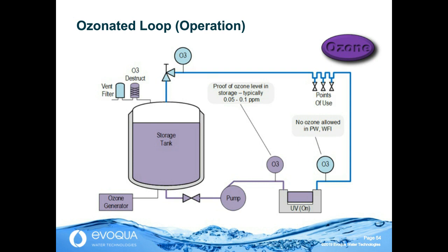Ozone is growing in pharma water at a very rapid rate. And here, this is a very simplified drawing, so it is not reflecting details of how the ozone is introduced into the tank, but in principle, the tank is always under protection of ozone in storage. It's monitored so that pre-ultraviolet light, a proper ozone level shows. In service mode, the ultraviolet light is on. There is no ozone in the water used in production.